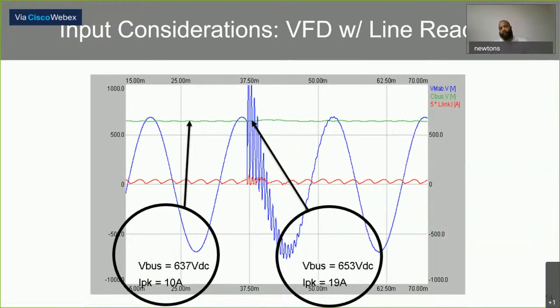You can mitigate that effect by adding a line reactor. Just by adding a line reactor to the input side of your drive, you can reduce the effect of the capacitor bank closing. Instead of your current increasing from 10 amps to 200 amps, in this case it's showing that your nominal was 10 amps, and when the capacitor bank closed, it went to 19 amps. So that's a lot more manageable. We'll get more life out of our VFD, less downtime, and that pretty much tells the story.